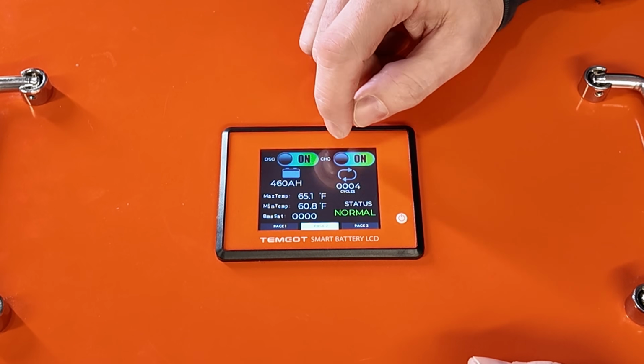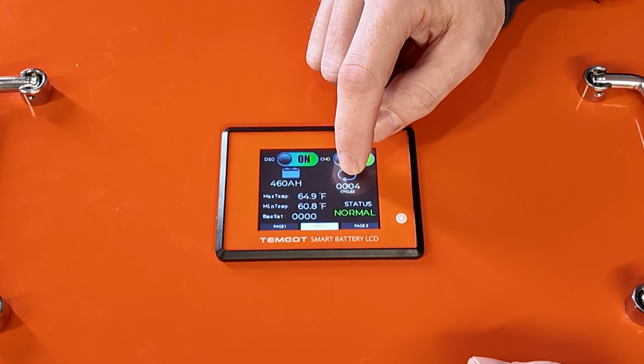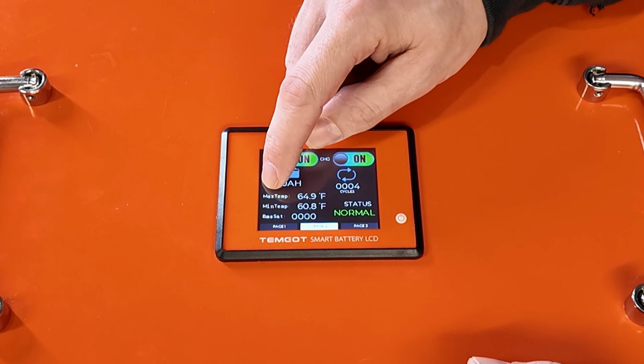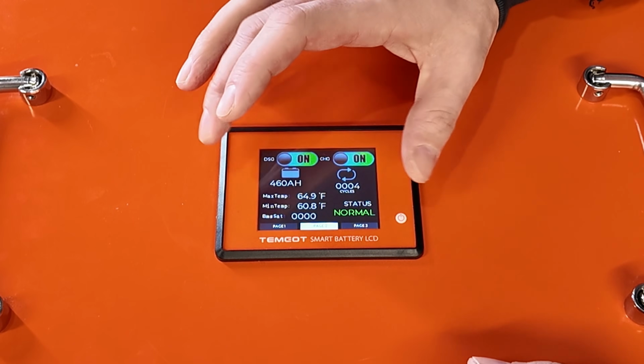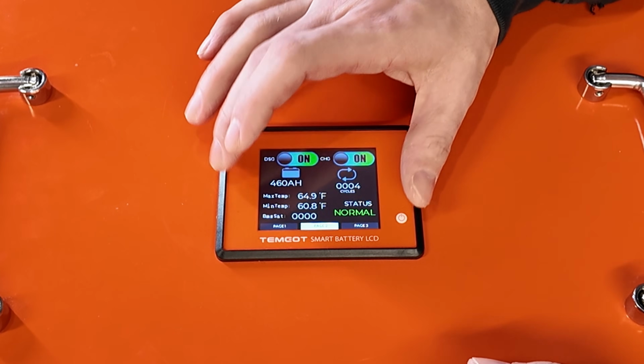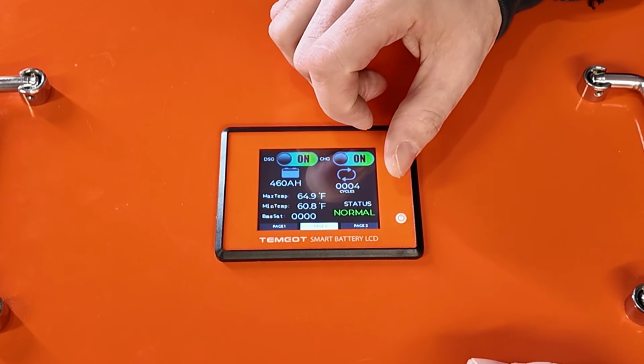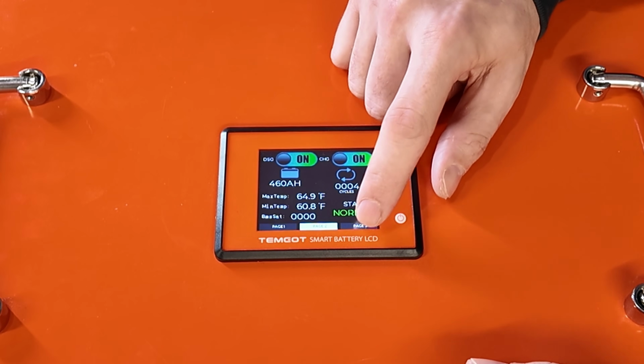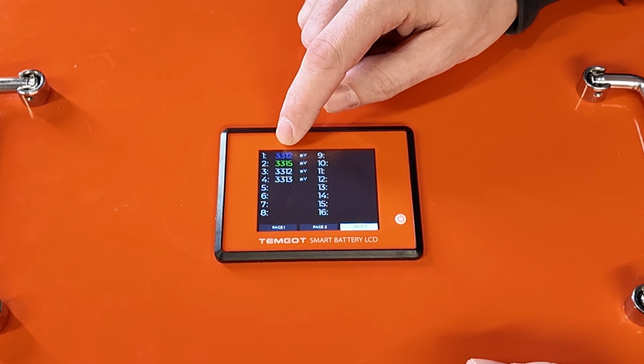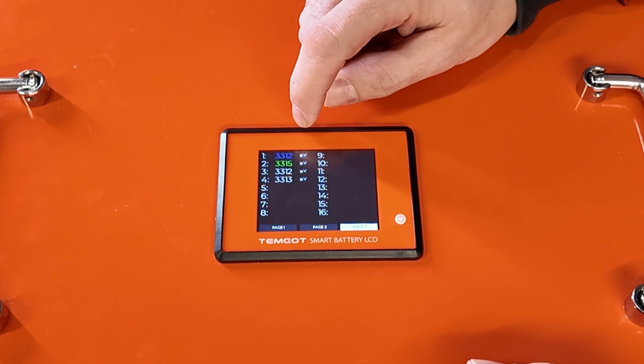And then we have 460 amp hours. This battery has been cycled 4 times. Our maximum minimum temperature, there are 3 or 4 temperature sensors in this battery. Our status is normal. Now if we come to page 3 here, it'll give you each individual cell voltage.